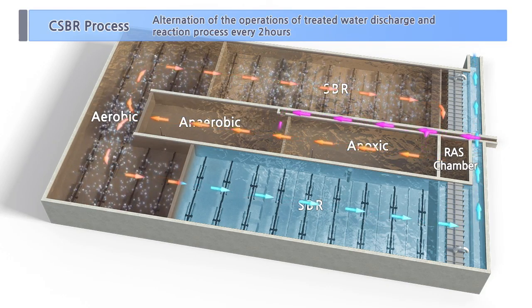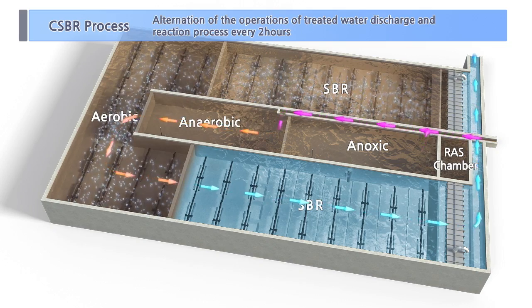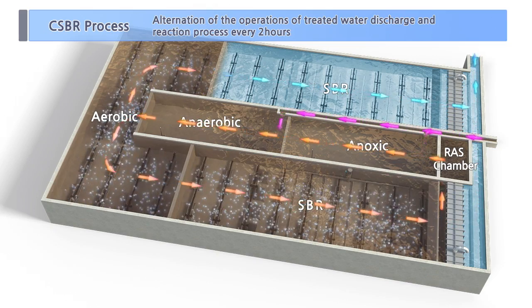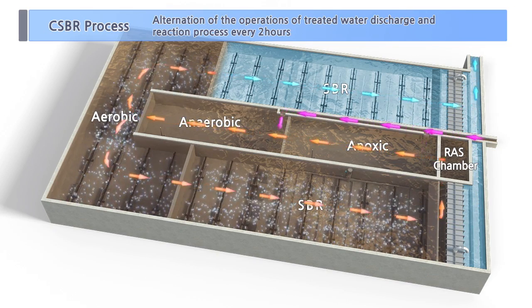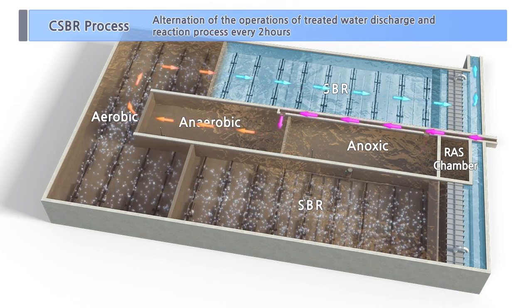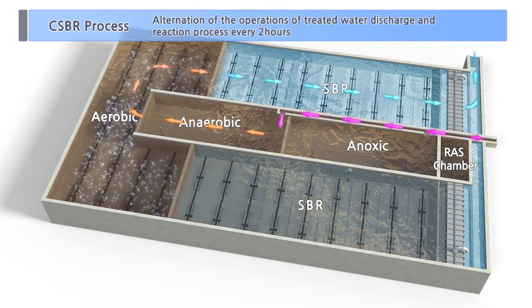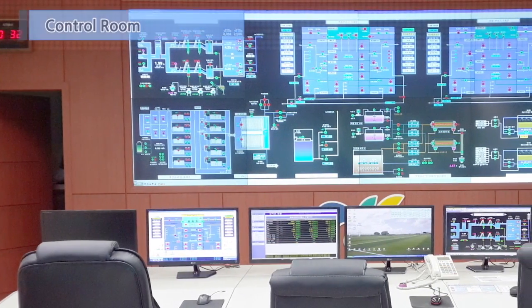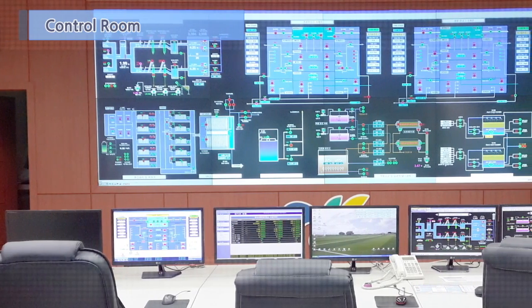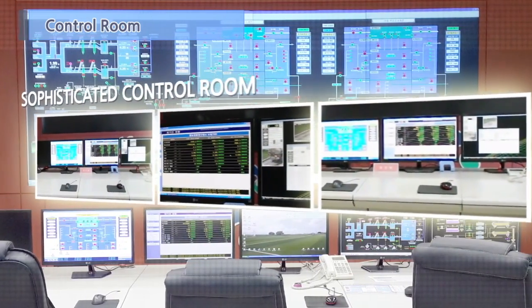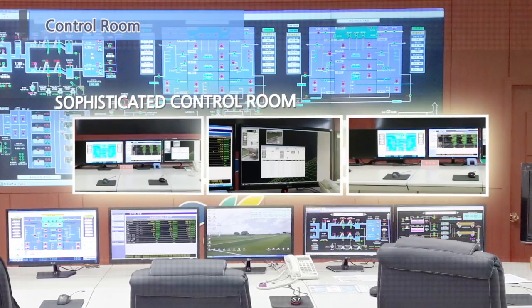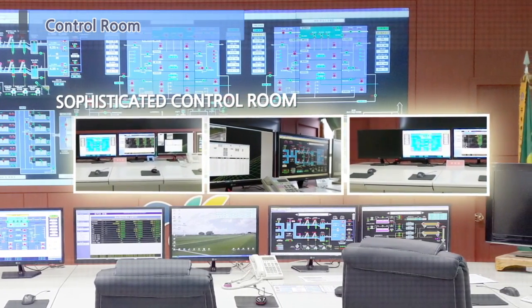Looking at the whole CSBR process: the A2O process of the anoxic, anaerobic, and aerobic cells operates 24 hours, while the two SBR cells alternately operate the discharge of treated water and reaction process for 2 hours per cycle. A PLC program automatically operates all the processes. The operator is able to work with the optimum condition suitable for the plant characteristics by adjusting operating conditions and checking the operation status through the monitor in the control room.